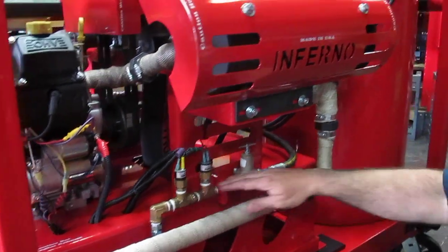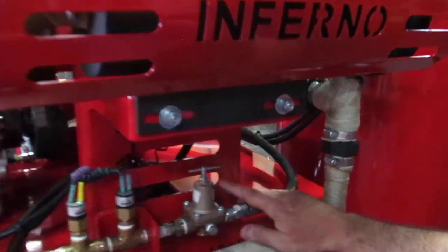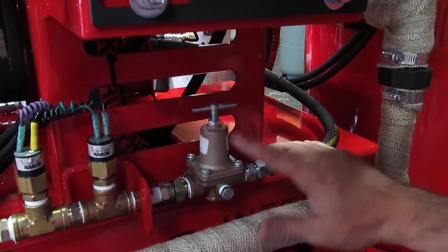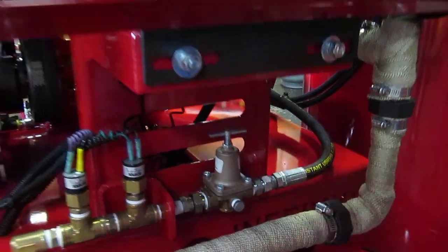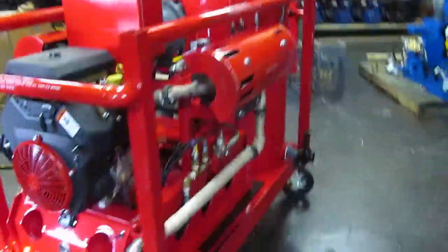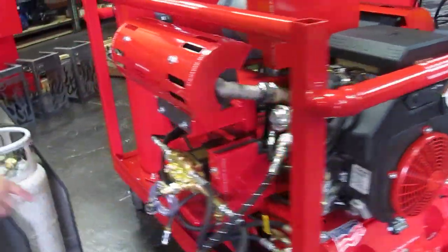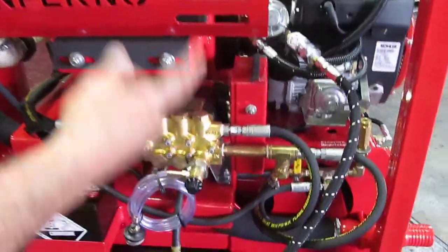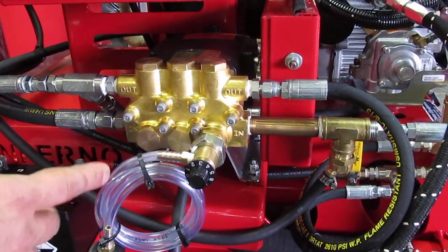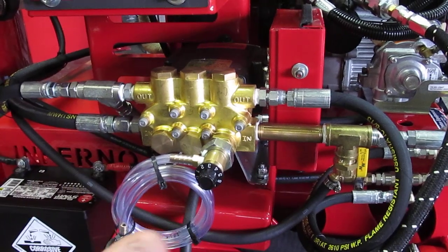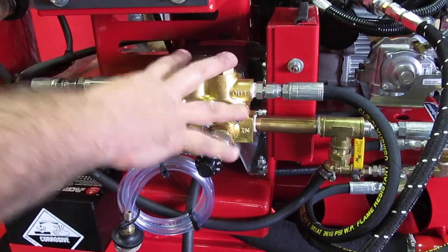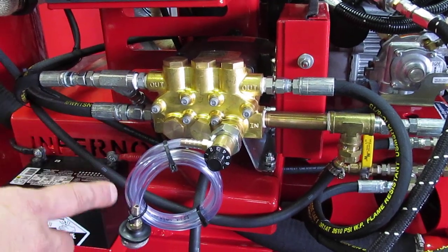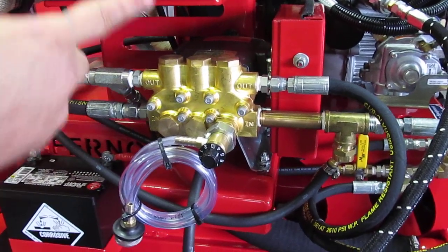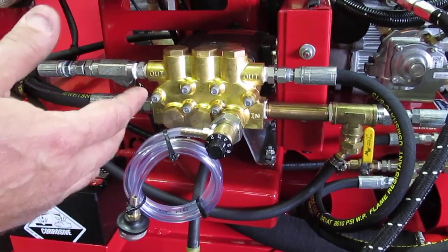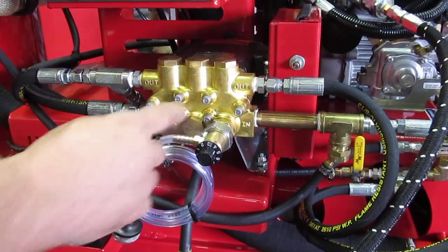Now, right past these switches, you run into an incoming water regulator. This is a very simple design that we've been using for years without any downtime. This baby right there, if we go to the left side of the machine, allows the injector, a simple injector that we've been using for years on our unit without any failure, to operate. How? With water pressure from different countries, different states, different cities, you run into different PSIs. In order for this pump to be able to do injection and self-priming, any incoming water pressure has to be 20 psi and below. That's why that regulator on the other side does the job. Any water pressure you give to this machine, it will reduce down to 20 psi and below. That way this baby will be able to inject chemical.